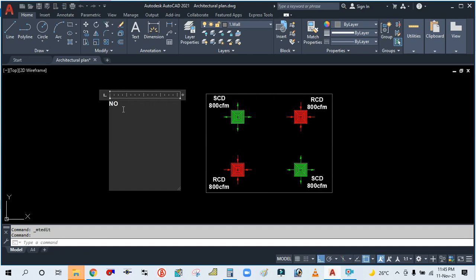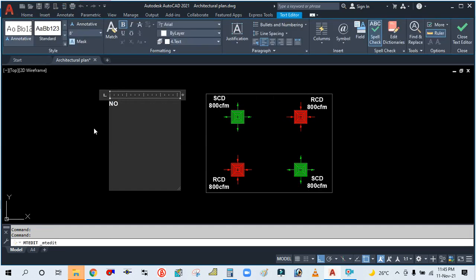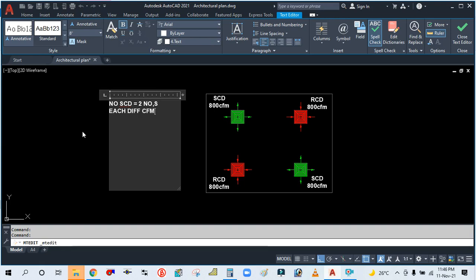So let's see how to size this. Number of supply ceiling diffusers is equal to two. Diffuser CFM is equal to 800. As per the continuity equation, we know Q is equal to A into V. Velocity for air terminal devices is generally considered 500 feet per minute.